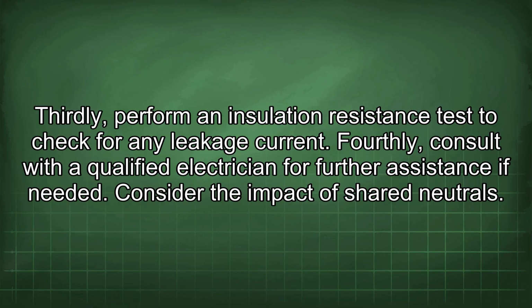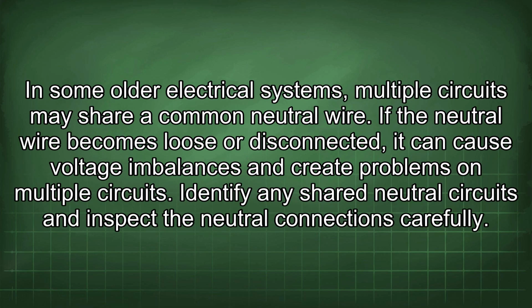Consider the impact of shared neutrals. In some older electrical systems, multiple circuits may share a common neutral wire. If the neutral wire becomes loose or disconnected, it can cause voltage imbalances and create problems on multiple circuits. Identify any shared neutral circuits and inspect the neutral connections carefully.